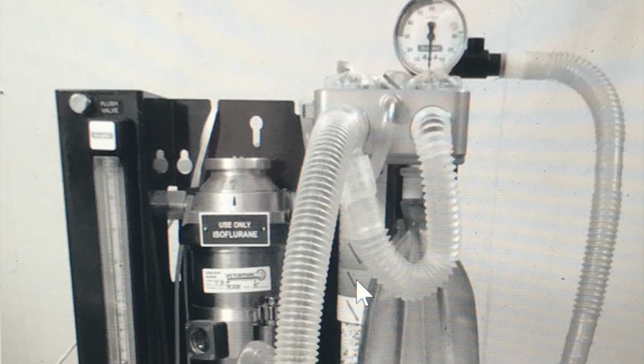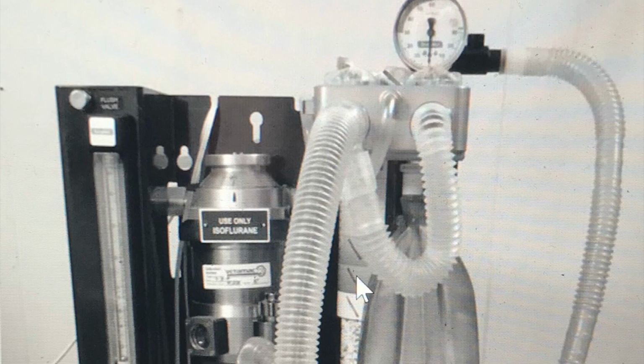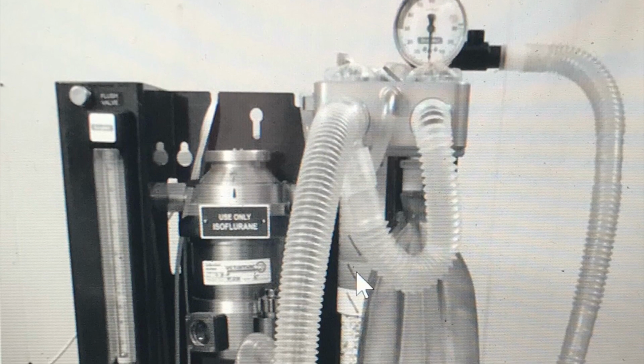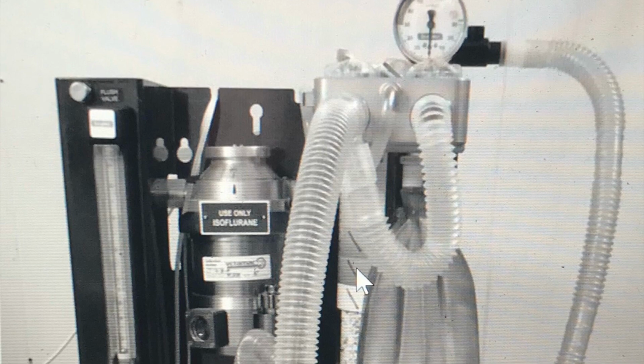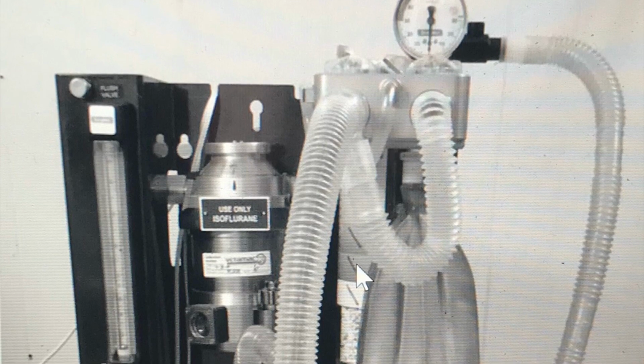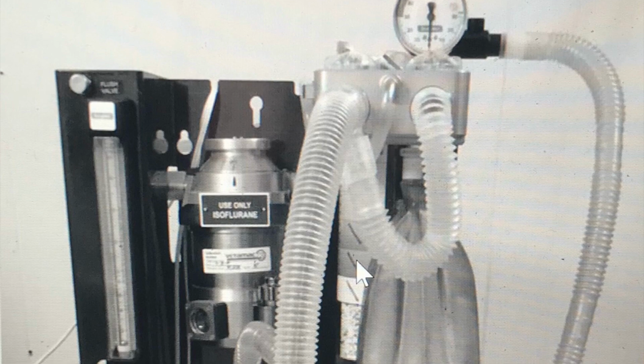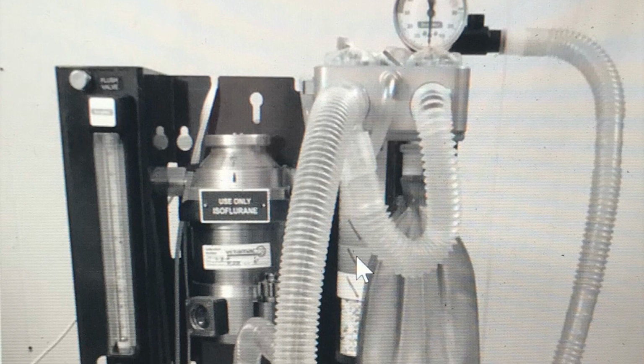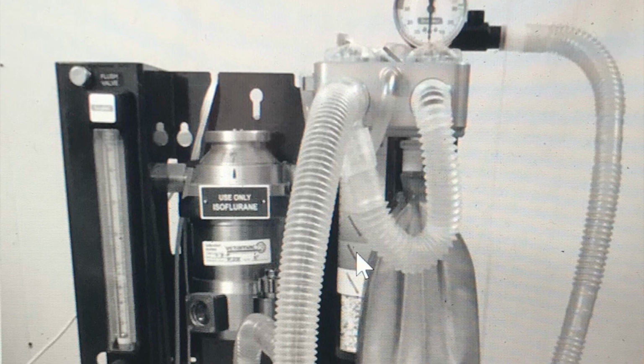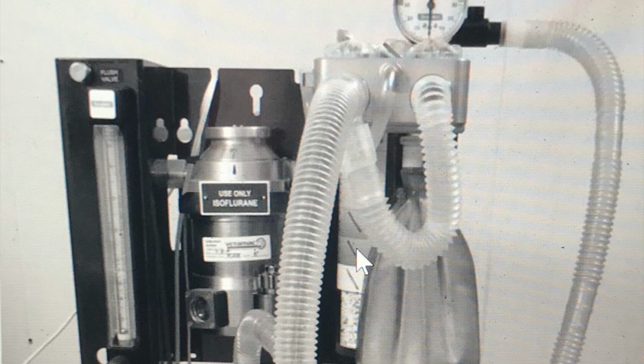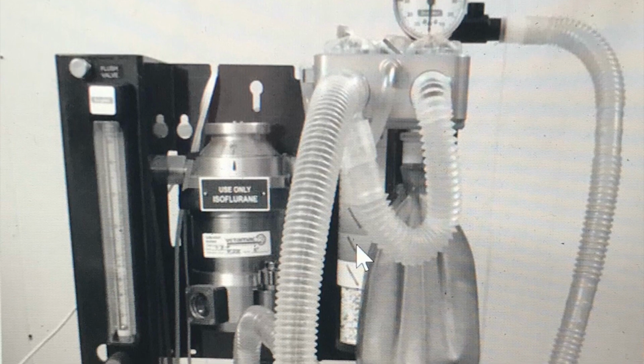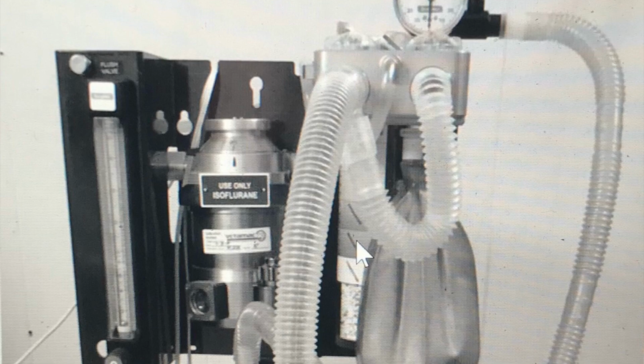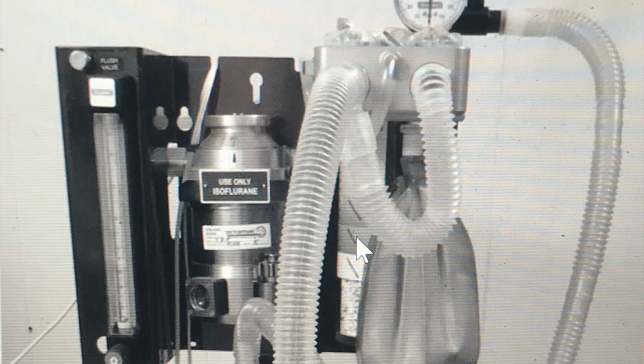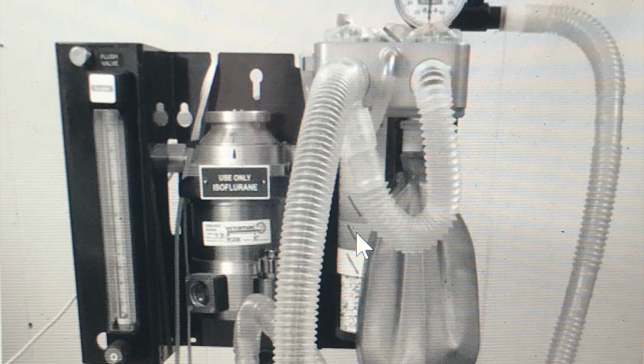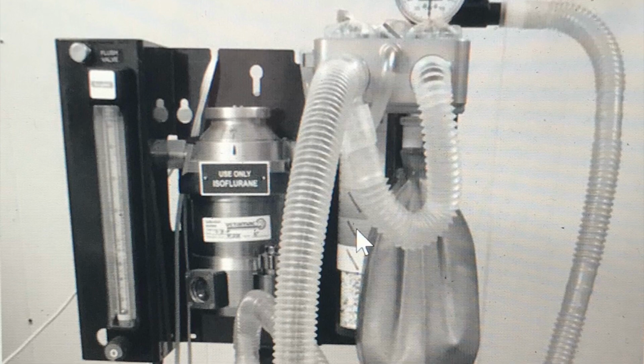This is the anesthesia machine, and it must be checked before using it for surgery. First, you will have to go into the oxygen room and check that the oxygen tank is above 500 psi. If not, you must change the tank. Then you will check the regulator pressure gauge and make sure that it is always reading 50 psi, as this is the pressure that goes into the anesthesia machine and it should never change. Also, if there is a change, there may be a leak in the line or someone may have left the flow meter on at the machine, so you might want to check this.